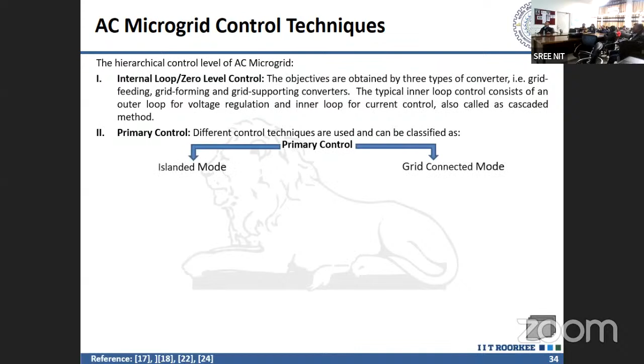So in AC microgrid, your primary control works in islanded mode and the grid connected mode, without communication and with communication. This is nothing but the elaboration of the previous discussion. So, like we said, our main control objective is whenever we are working in the islanded mode. Without communication, we have the conventional droop and the improved droop application. Droop application we will see. With communication, we will have the concentrated control, means all information we are getting at one point. Any question? If you don't understand the meaning of anything, we can discuss.